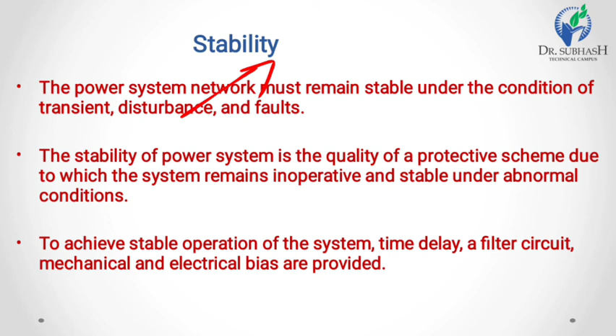Now, stability. A protective system should remain stable even when a large current is flowing through its protective zone due to an external fault. The concerned circuit breaker is supposed to clear the fault, but the protective system will not wait indefinitely if the protective scheme of the zone in which the fault has occurred fails to operate. After a preset delay, the relay will operate to trip the circuit breaker. To achieve stable operation of the system, time delay, a filter circuit, and mechanical and electrical bias are provided.